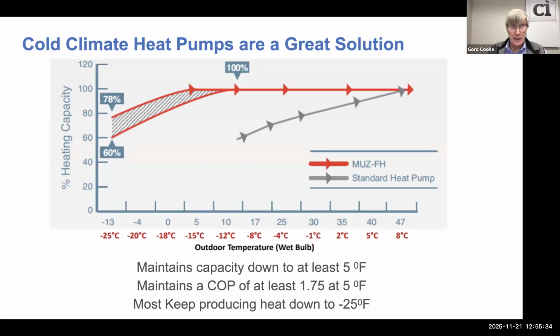Here's the definition of cold climate heat pump. Maintains its capacity nominally down to 5 Fahrenheit, maintains a COP, remember, COP is watts out versus watts in, of at least 1.75. Even at 5 Fahrenheit, it's 175% efficient. Can I say that again? At 5 degrees Fahrenheit, cold climate heat pumps are still working. For every dollar of electricity you buy, you still get $1.75 worth of heat into the house. And most keep producing heat down to as low as minus 25. Then you simply ask the manufacturer, do you have a cutoff temperature?